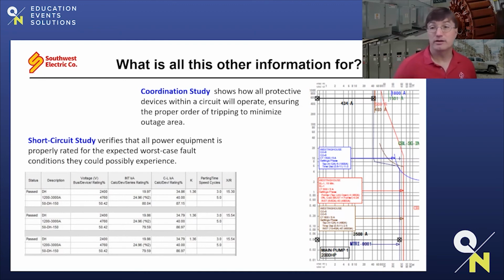There's also a coordination study that is included in this assessment. This overlays all the different protective curves throughout a given circuit to make sure everything is coordinated, so that the lowest level disconnect would trip first before a higher level or upstream disconnect would trip. Think about it in your house. If you have an overload on a receptacle, you wouldn't want the main breaker to trip first. You would want just that breaker feeding that receptacle to trip and leave all the other loads maintained. Same thing here. A proper coordination study ensures that the lowest affected area would be tripped in order to clear any kind of fault that is detected.